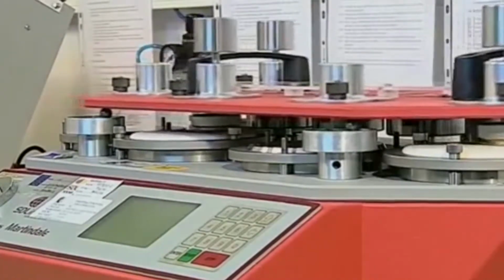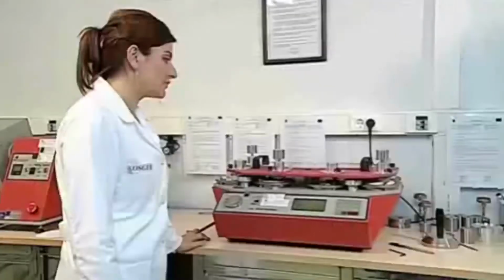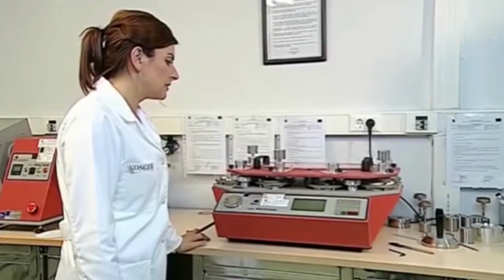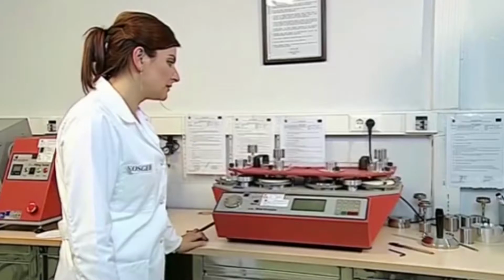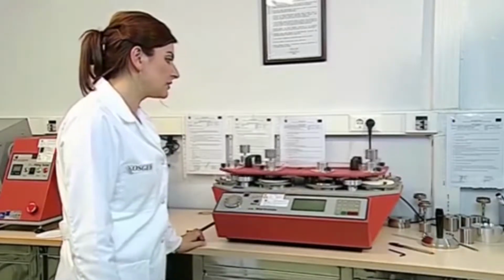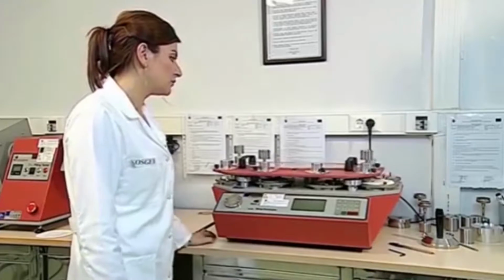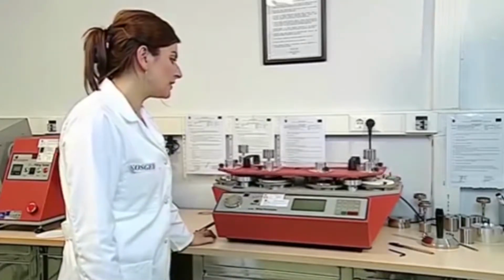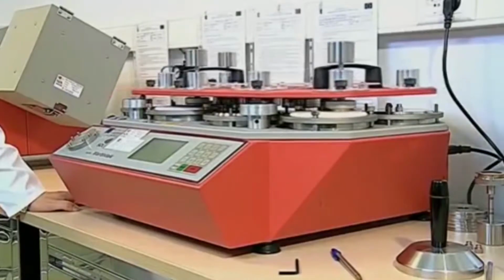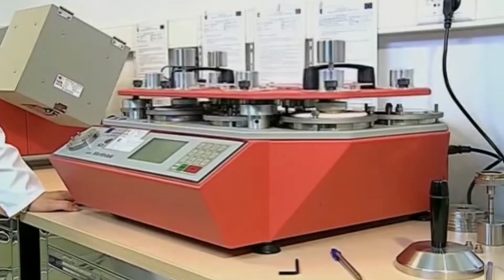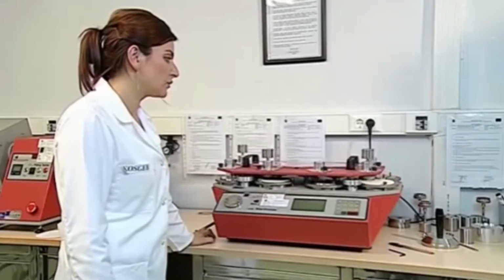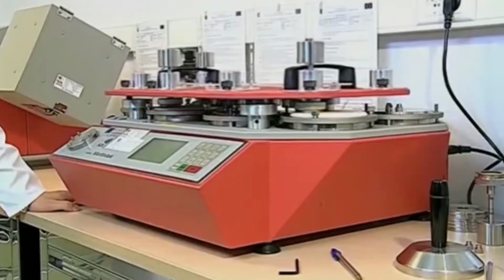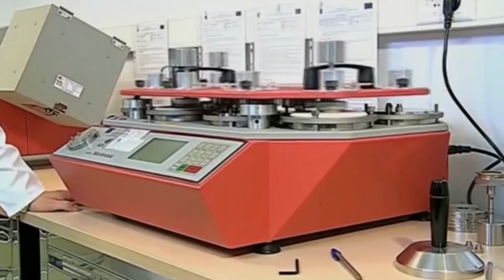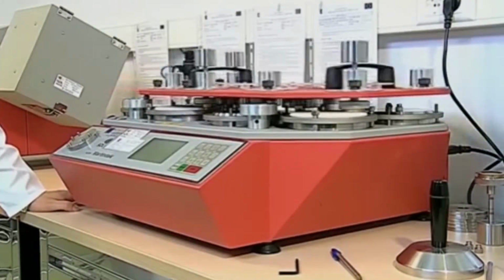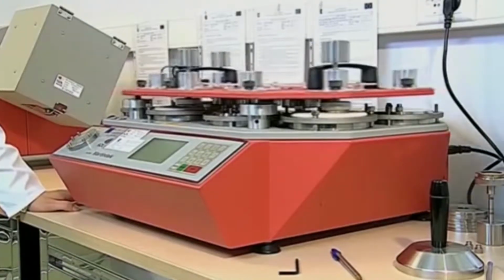We will check the samples at certain intervals. At the end of 2000 cycles, the device will automatically stop. We use an 8x magnifying glass or loupe to check the breaks. And when there are two different weft or warp yarn breaks, we end the test. If there is no abrasion when we check it, we enter 2000 again and go on to the abrasive friction. We stop the test after the sample breaks.